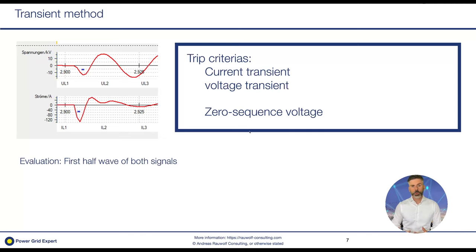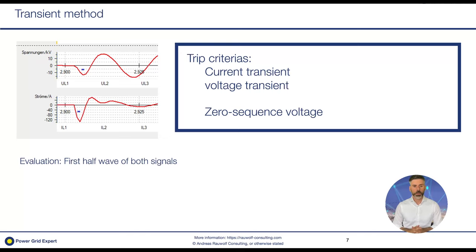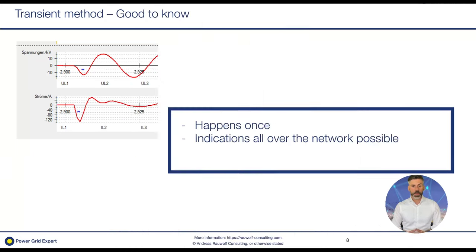Sometimes an additional criterion is added to filter out pure transient earth faults not followed by a static earth fault. For example, in an overhead network a bird or a tree branch may cause a brief transient. Some operators may not want any indication for that since it's not a static earth fault. We can filter out these pure transient faults by checking whether a 50 Hz zero sequence voltage is present after the transient. As a summary, this is quite a stable method.